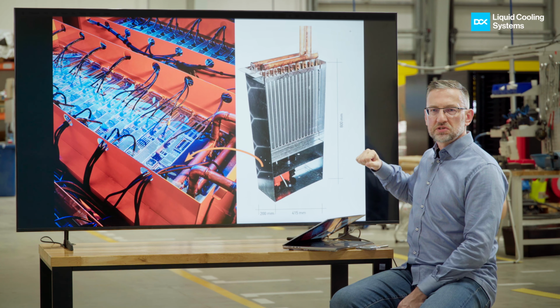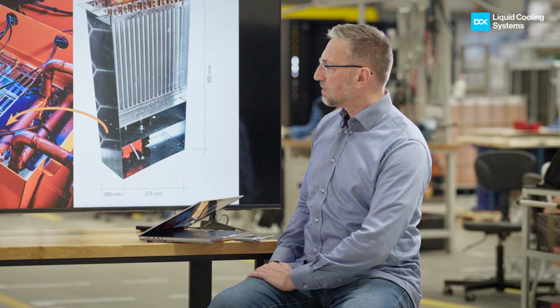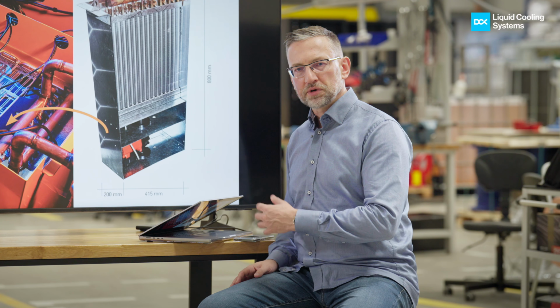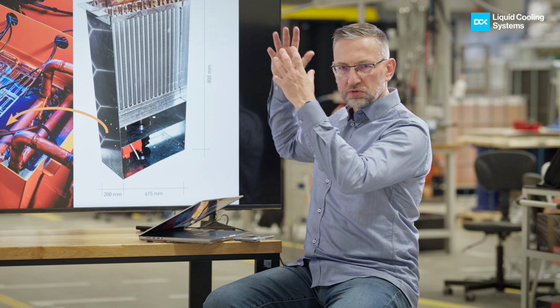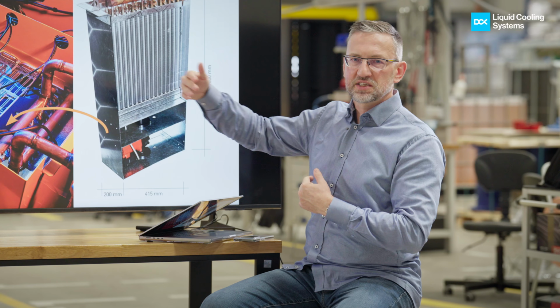And as far as I know, they had litigation with another supplier, which took the same tank, packaged it inside, and just named it CDU. It's not a CDU. Is that the best solution? In my opinion, no, because for the eventual replacement of the pump or anything, you actually need to remove that unit. So basically, it affects the server.